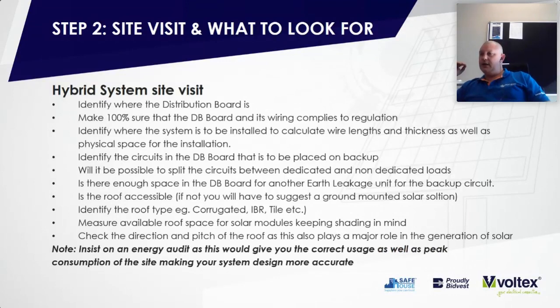Measure the roof space. A hybrid system can be calculated to power the full load or split the load. So once again, you need to establish if there's enough space in the DB board for another earth leakage if you do load splitting. Or in the event that you're going to run the whole system from the alternative energy source, you do not require space for an alternative earth leakage. You can run it through the main earth leakage.